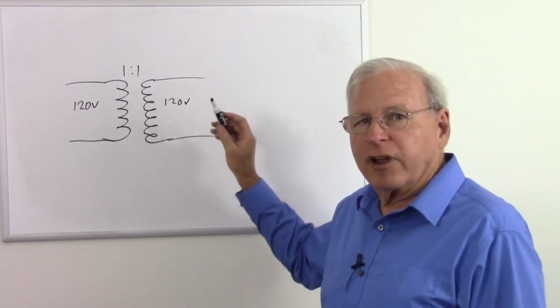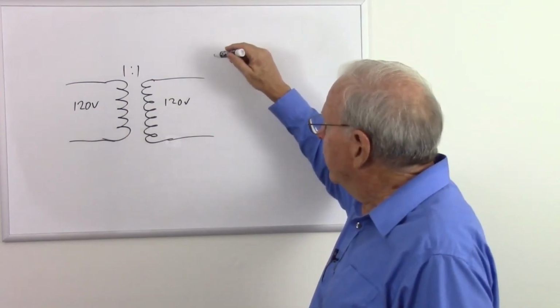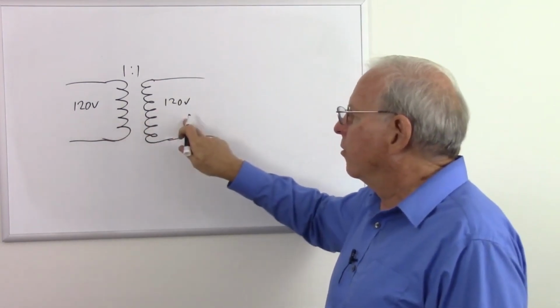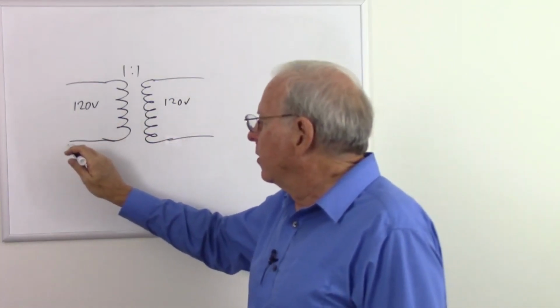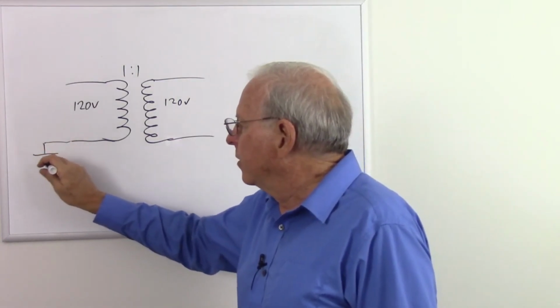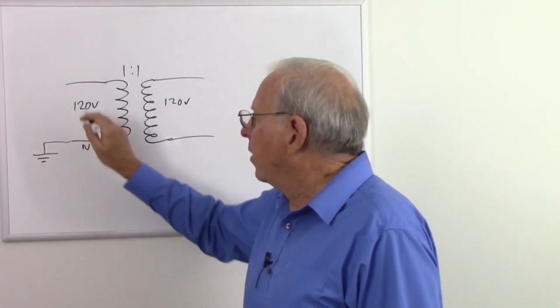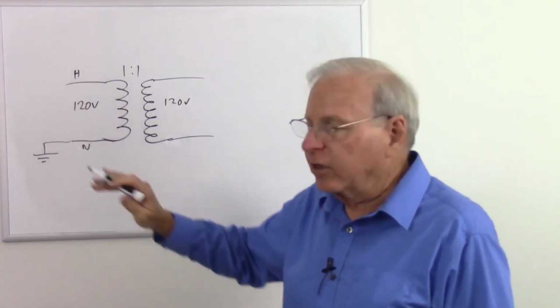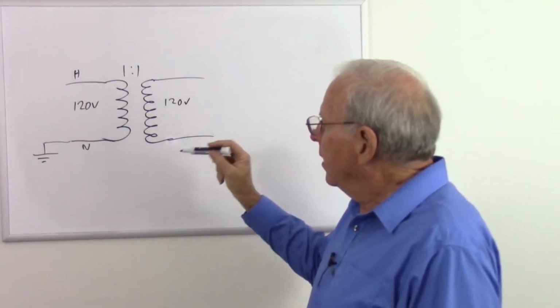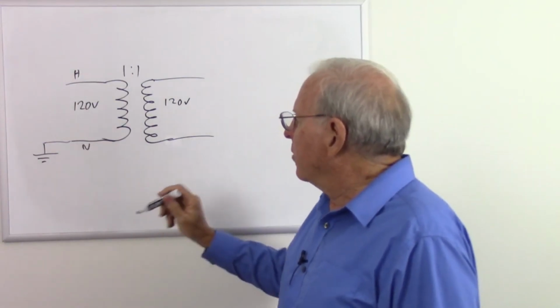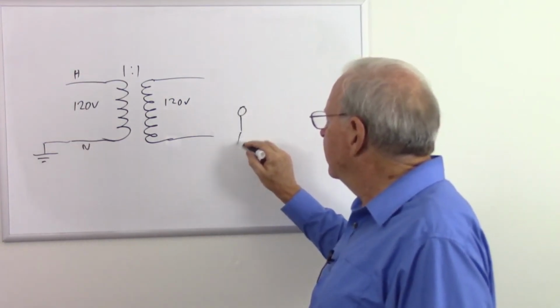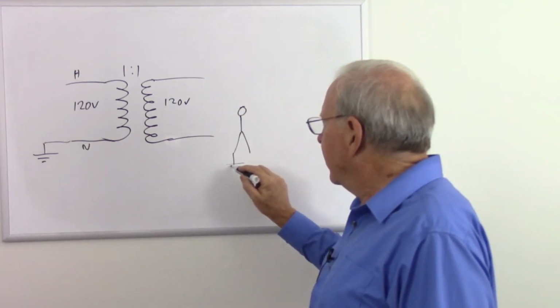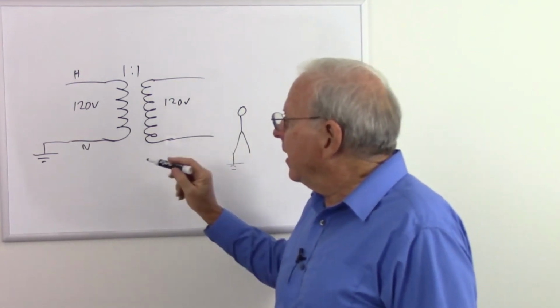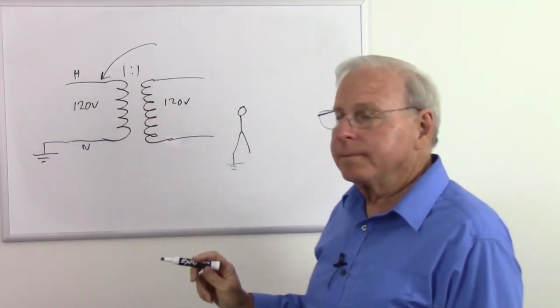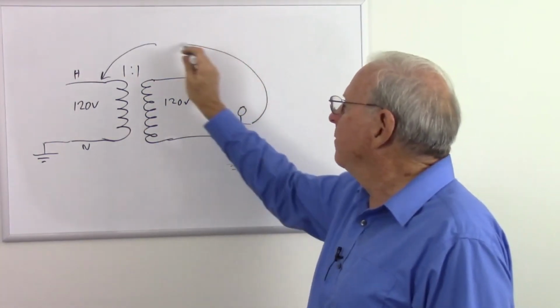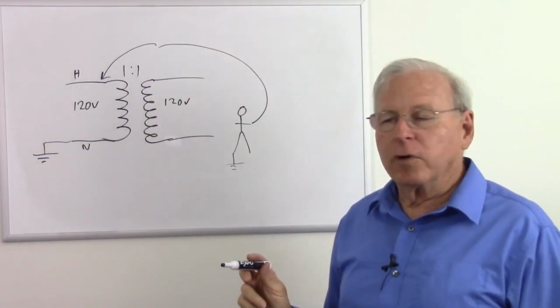Another purpose of isolation transformers is safety. Let's look at the secondary over here — 120 volts in, 120 volts out. Over here, somewhere this is grounded. I'll just ground that there. Let's say that's the neutral wire and that's the hot wire. I go into more detail on this in another video linked below. But here I have a ground, and here's me also connected to ground. If I touch this one wire somehow while grounded, I get 120 volts across me.